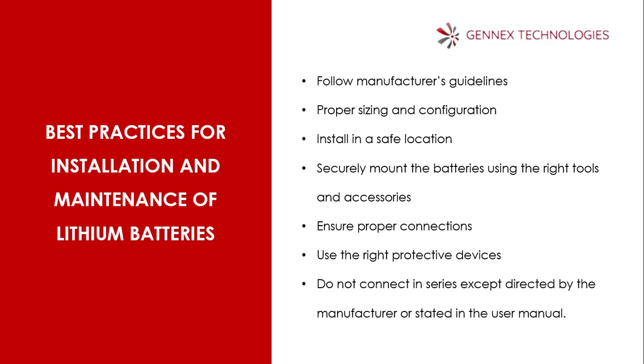It doesn't mean you should put a 10,000 watt load on a 10 kilowatt hour battery just because it's labeled 10 kilowatt. People misunderstand this, it's not like that. Get a standard design, let it be thorough. You can't be 100% accurate, but do something that will work. So proper sizing of all components around the system is very important.